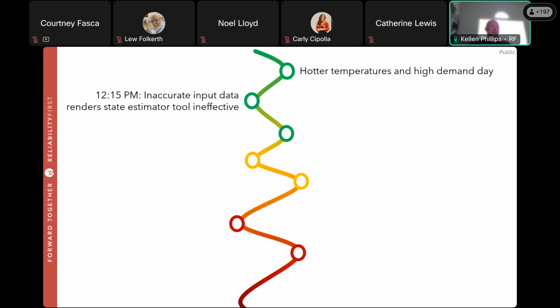For those less familiar, the state estimator tool feeds into the RTCA, or real-time contingency analysis, the "if this happens, what happens next?" For example, if this line trips, where do the remaining megawatts go, and does it overload any other lines? What if this generator trips, and so on and so forth. Whether there's a big change in the power system, the operators will run the tool to analyze those contingencies. The issue here is that the state estimator is down and effectively the RTCA is down with it. The operators can't see what potential outages could happen, potential overloads, and so on.